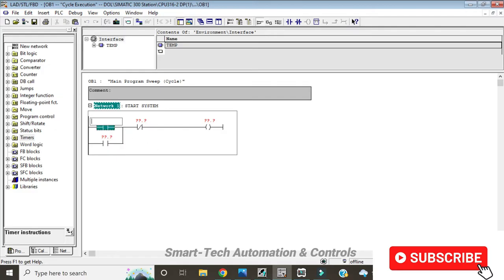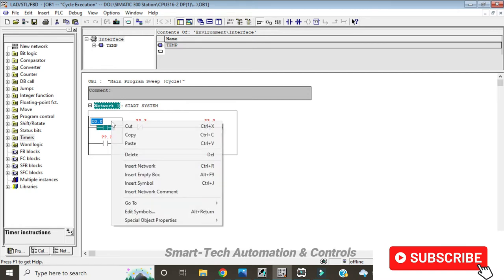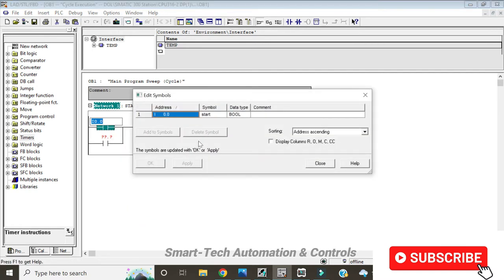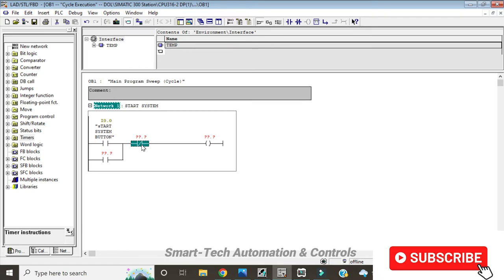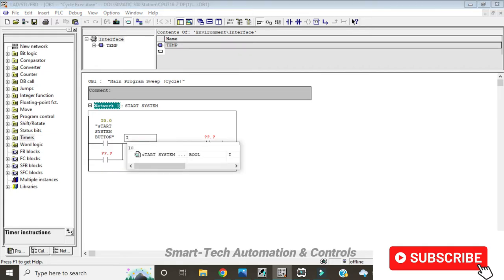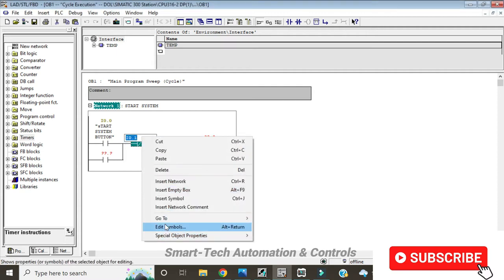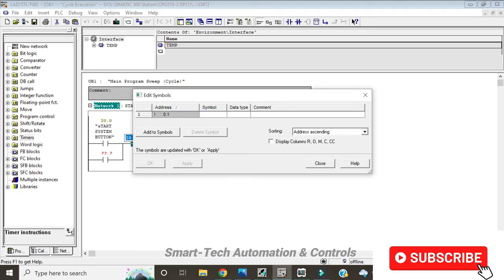I'll give them addresses. The address for the first normally open contact will be I0.0 and for the symbol we can call it start system button. Okay. For the normally closed contact, here we'll give it address I0.1, and for the symbol we call it stop system.